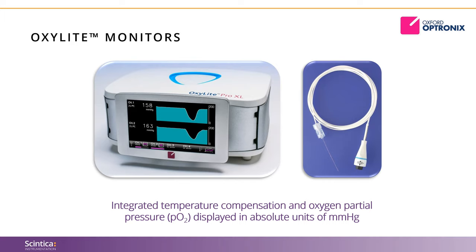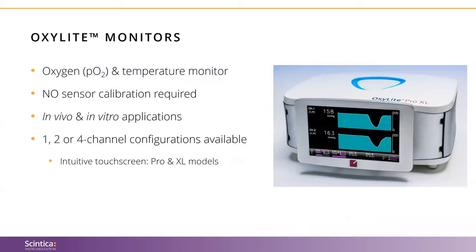My colleague Sydney will now review the world's most user-friendly dissolved oxygen monitor for in vivo and in vitro PO2 measurements. In 1998, Oxford Optronix pioneered the commercialization of fiber optic oxygen microsensor technology. The fluorescence-based technique employed by the OxyLite monitors provides integrated temperature compensation and absolute measurements of dissolved oxygen displayed in absolute units of millimeters of mercury. Today there are over 500 peer-reviewed journal citations of the OxyLite brand. There are three models to choose from dependent upon your research objectives: a single-channel system and two different multi-channel systems.